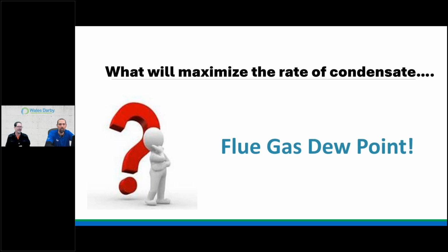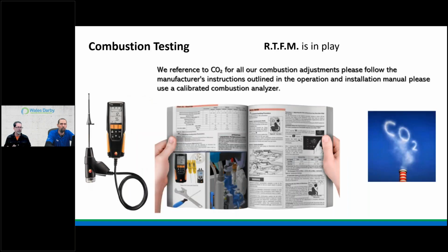Yeah, right, low flue gas return temps. It's the flue gas dew point, right? So understanding when we're setting up this boiler, right? Okay, so a lot of manufacturers say how they test and calibrate, and then they ship it to wherever it's got to go in the world, right? So now we have different air quality, we have sea level change, we have gas quality change, right? So now it's the due diligence of that installer, not just at the installation either, but maybe in tune-ups and all, to do what? You've got to read the manufacturer manual, right?